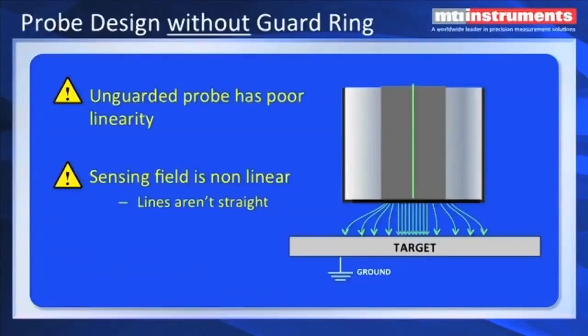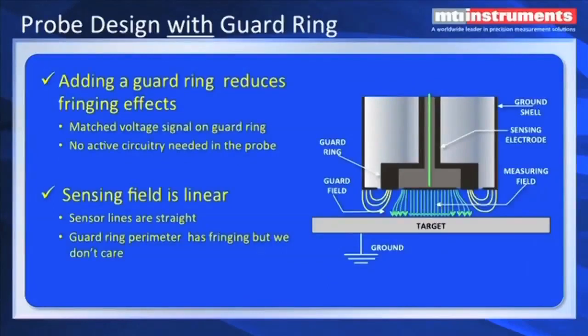The other thing we have to deal with is the guard ring on the capacitance probe. A capacitance probe without a guard ring has field distortion. If we look at the probe in the image here, we can see the center electric field is fairly straight, but as you get to the edges of the plate, we have what's called fringing, and the field starts to distort. Well, that contributes to linearity error, and that's bad. So what we want to do is get rid of that fringing effect on the center plate to the target. The way we do that is by adding a guard ring. The guard ring is run at the same potential as the center electrode, and it linearizes the field.